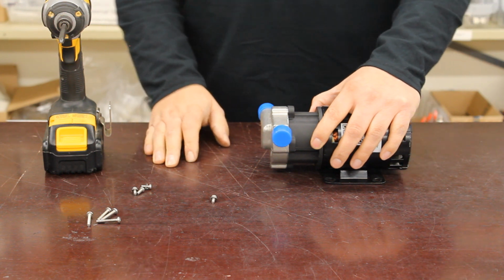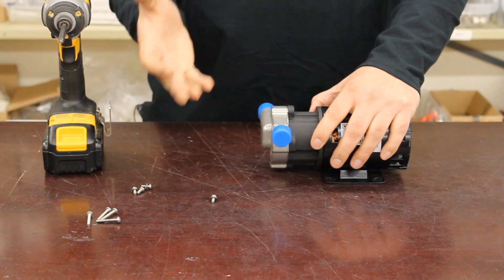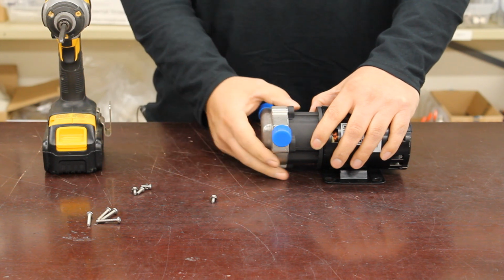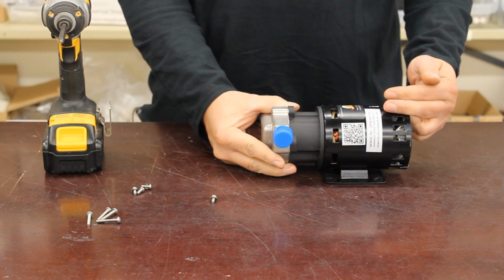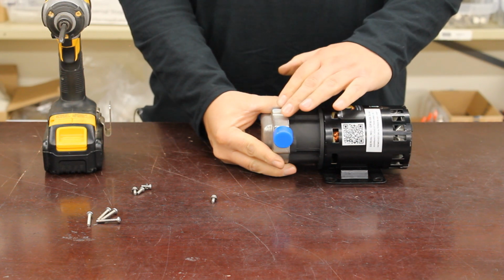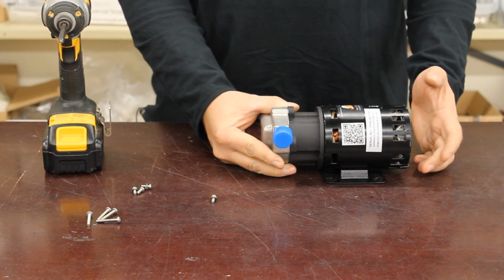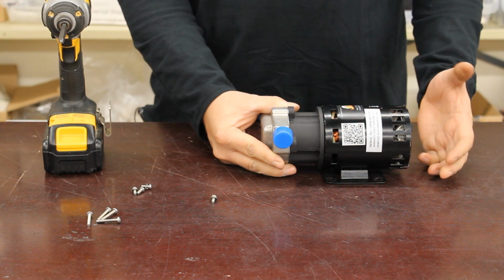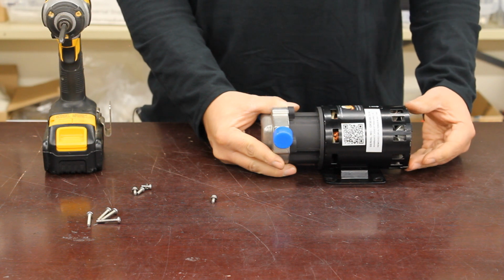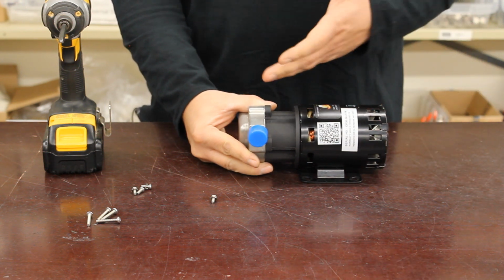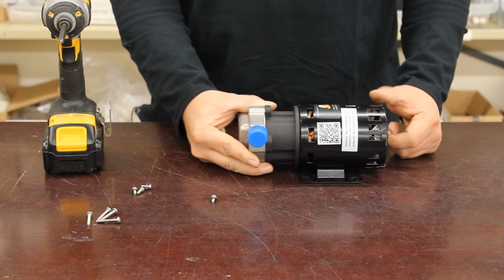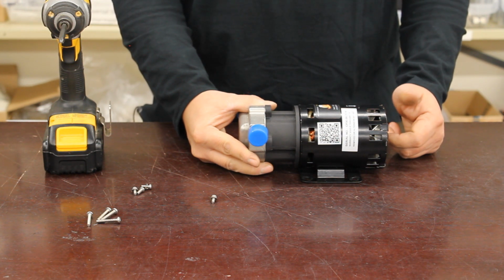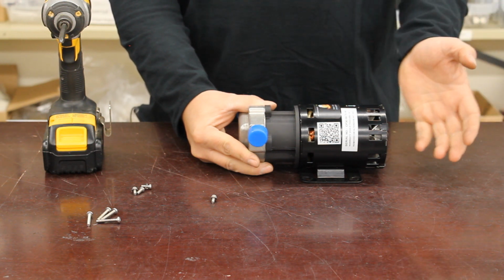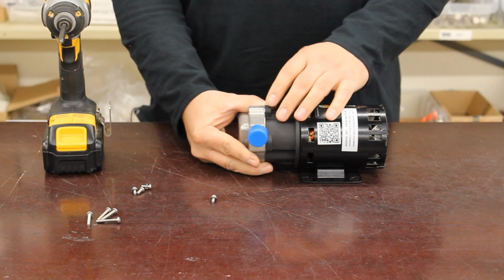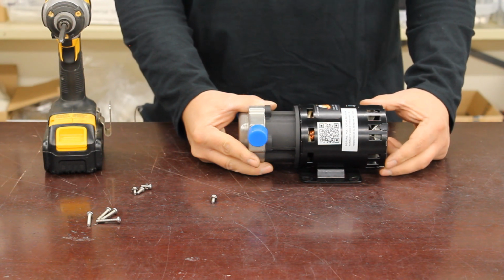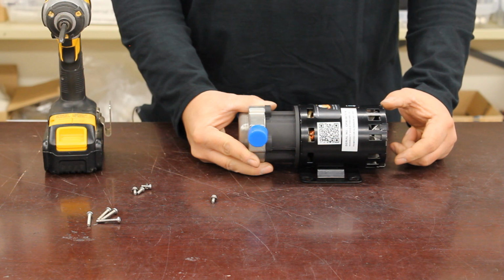Now, the last scenario that we may need to troubleshoot is what's known as magnetic decoupling. That can be described as the condition where the motor's spinning just fine, the head and its internal components have been verified as clean, and the impeller is free spinning, but no matter what you do, you can't get this pump to move any liquid. Discounting the fact that you may not have the pump fully primed, the last possibility is that the cup magnet is not conveying strong enough magnetism to the impeller magnet, and therefore it's losing its coupling.